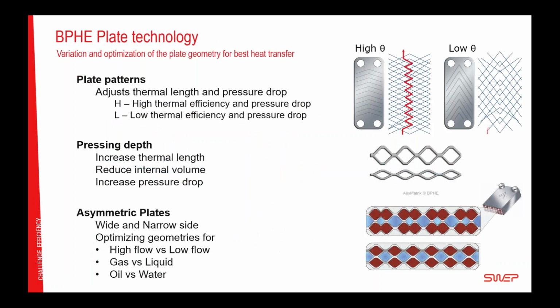So, the easy, the hard and the tricky heat transfer cases. The tools that SWEP have developed in our models to meet requirements like that are included in H and L type plates, high thermal length and low thermal length plates. In the high thermal length plates, the flow has to follow a longer path inside the heat exchanger, making more pressure drop, but also more heat transfer. In a low thermal length plate, the path is quicker, less pressure drop, but also less thermal length.